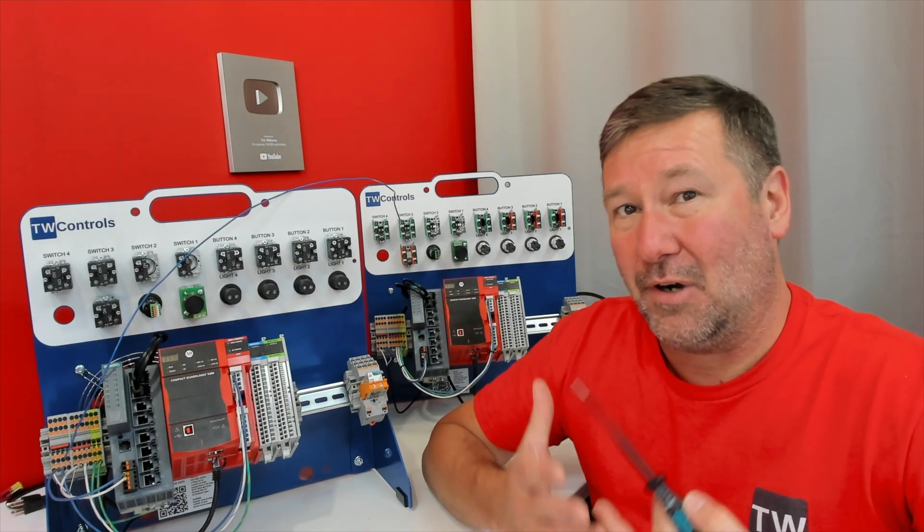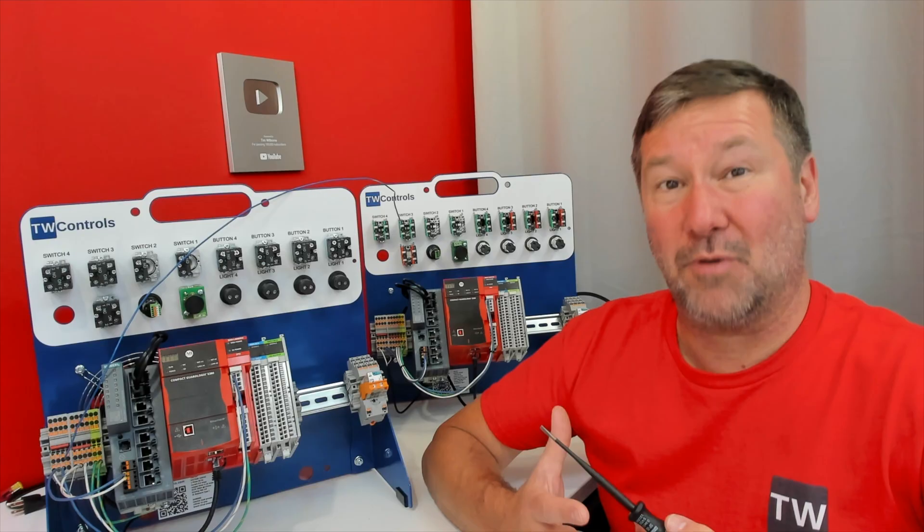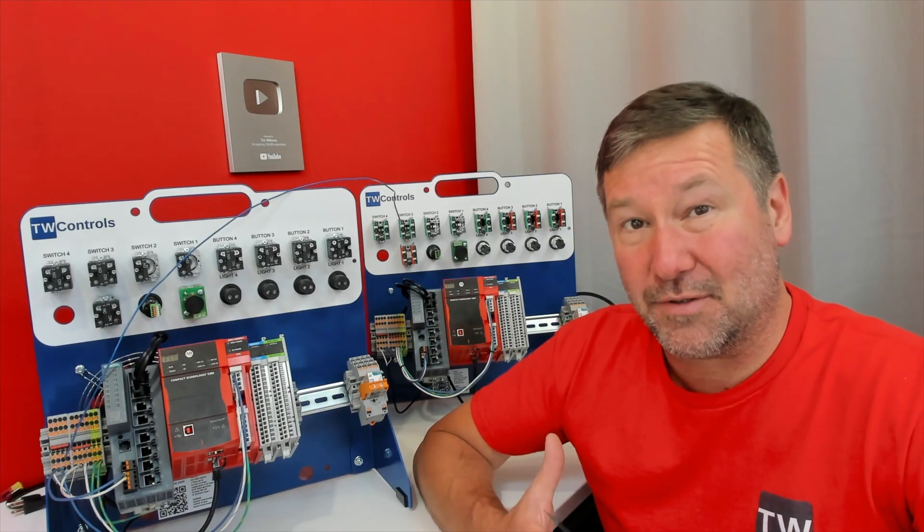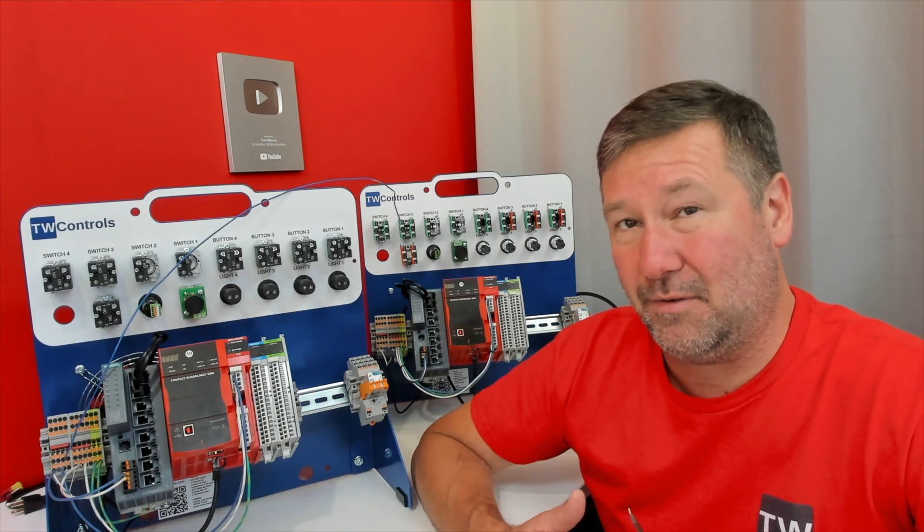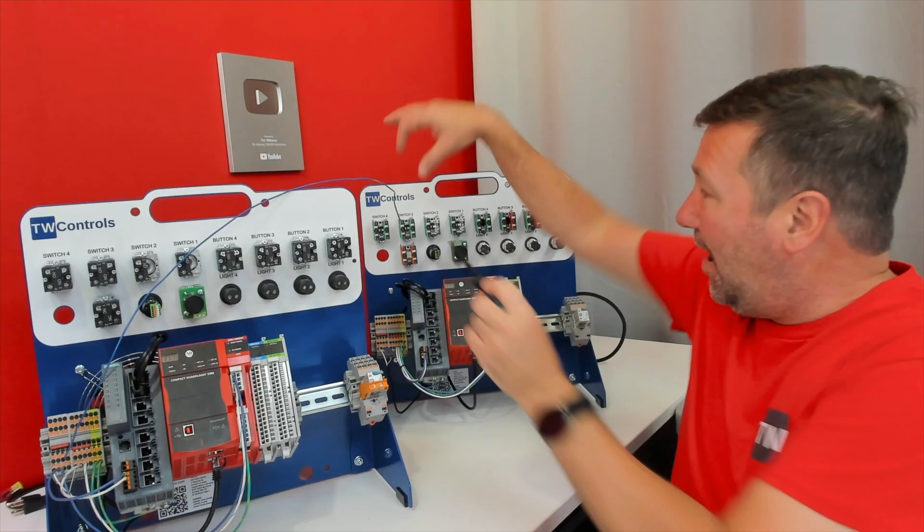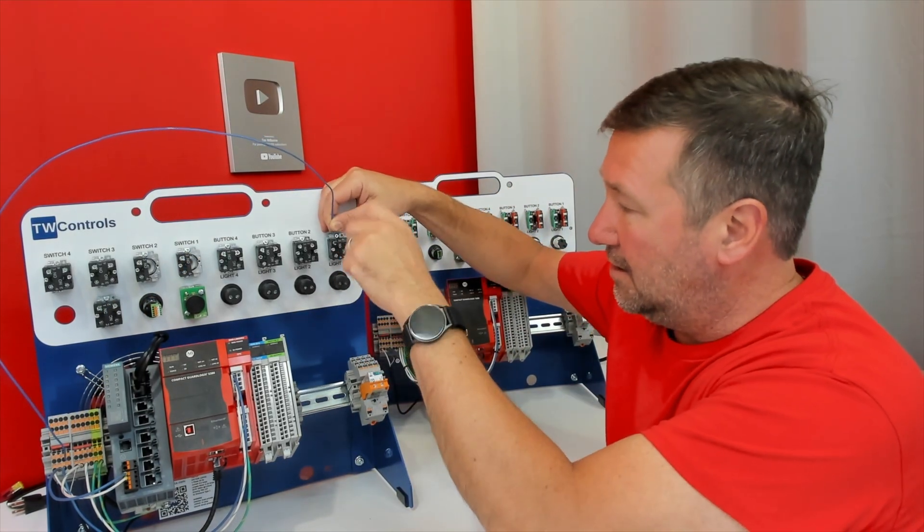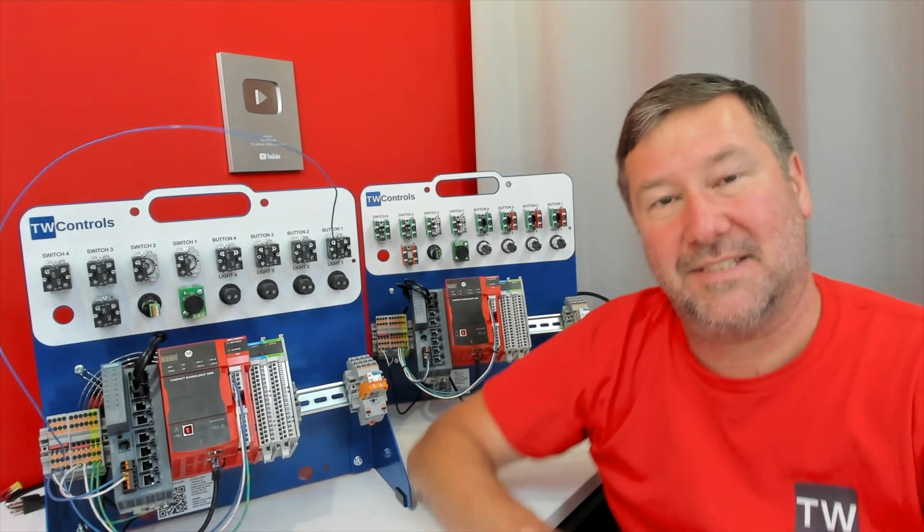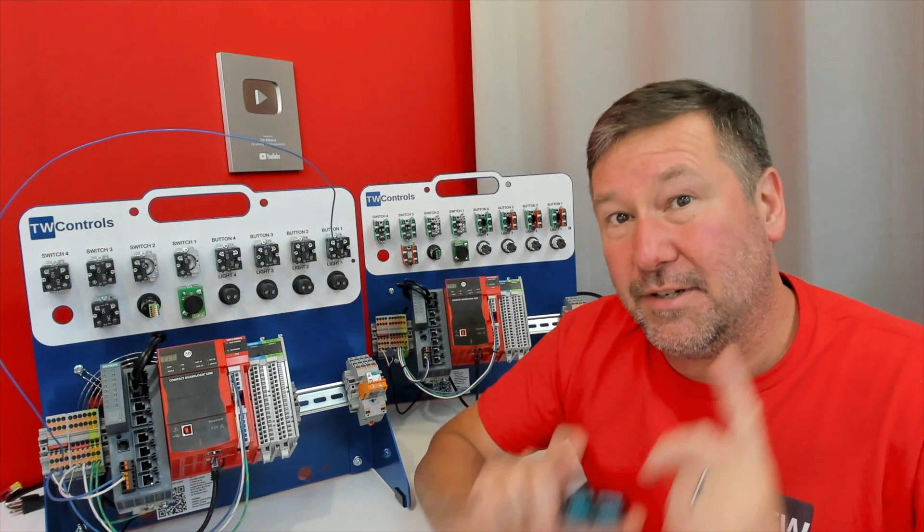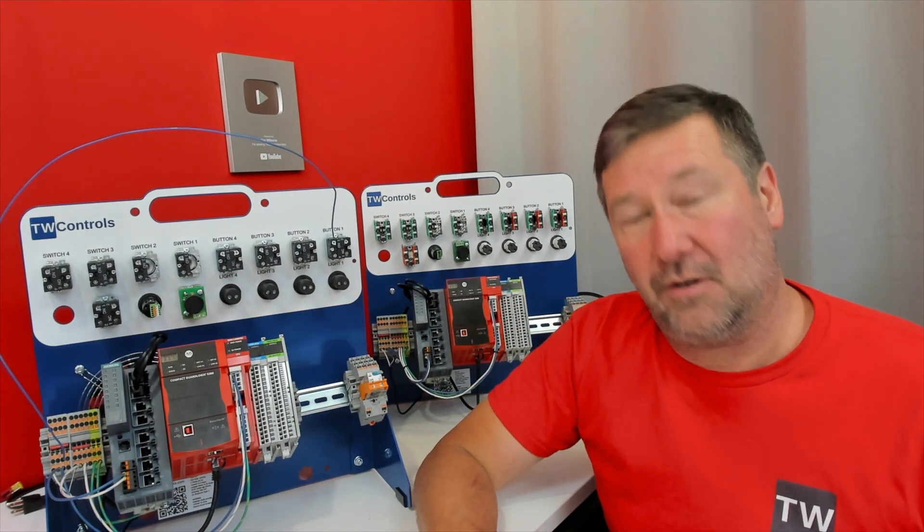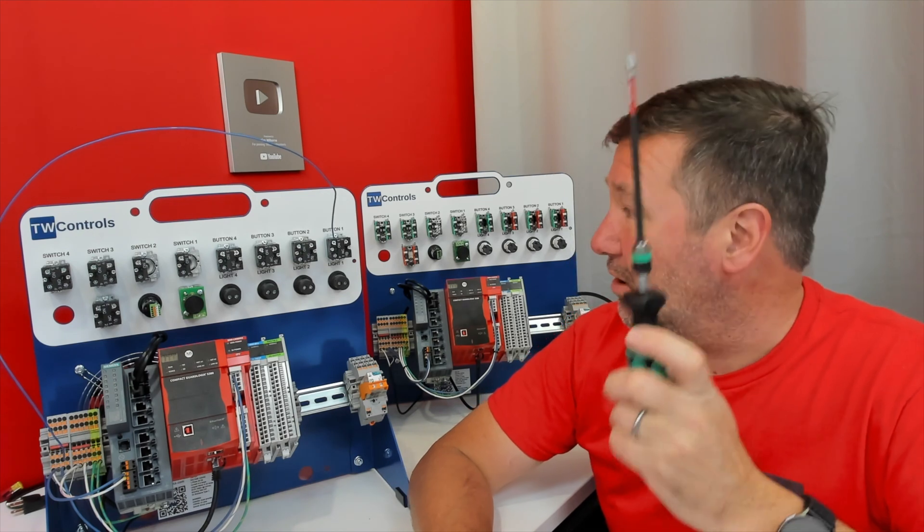As a panel builder, our goal really is to get rid of as many screws as possible in our control panels, because it's not okay to simply put a wire into here, twist it, give it a little twist and say, we're done. Every screw in your control panel has to be properly torqued.